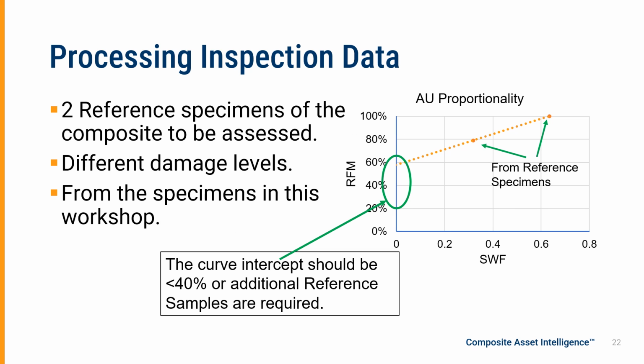So, for example, I'm giving this chart here, and I'm calling it an AU proportionality curve, where I've got 2 reference specimens. One with an RFM of 100%, so it's from new equipment, and we've got a stress wave factor of just over 0.6. The second one, we have an 80% RFM value, so it's been in service for some period of time, and we have a stress wave factor somewhere around 0.35 or something. Essentially, we look at a pretty much linear relationship between RFM and stress wave factor. So if we connect those, we come up with this curve.